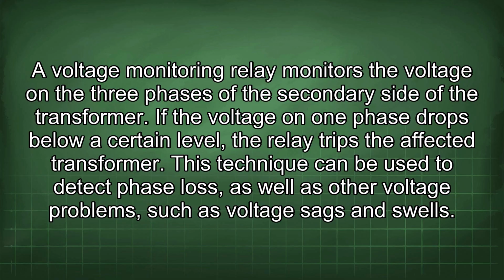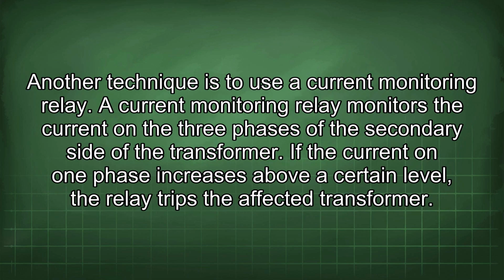This technique can be used to detect phase loss, as well as other voltage problems, such as voltage sags and swells. Another technique is to use a current monitoring relay. A current monitoring relay monitors the current on the three phases of the secondary side of the transformer.